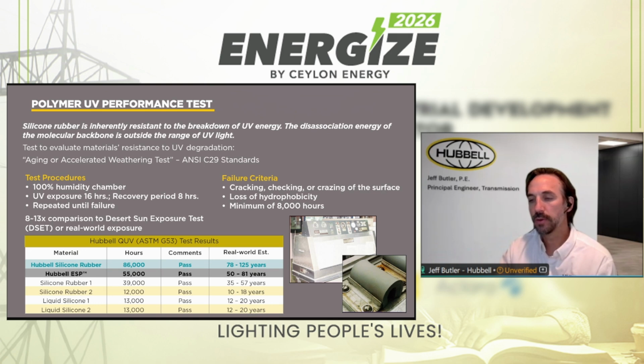But the other interesting note was the difference between silicone rubber 1 and silicone rubber 2, which should have been similarly qualified, similar performance polymers, and yet we saw a dramatic difference in the performance of those two rubbers. So it just speaks to, even though a silicone rubber may be commercially available, may be manufactured by a given company, there could be dramatic differences in the performance of those materials, and that needs to be investigated. And then taking those times and estimating real-world exposure, that's the column on the right. But again, this does refer to just UV exposure. So this doesn't take into account a lot of the other environmental conditions, contamination, coastal environments, whether you're exposed to salt, perhaps industrial contaminants. So we're not saying that a Hubbell silicone rubber insulator should last 125 years.